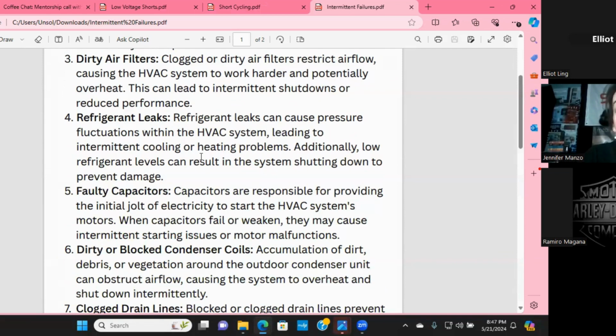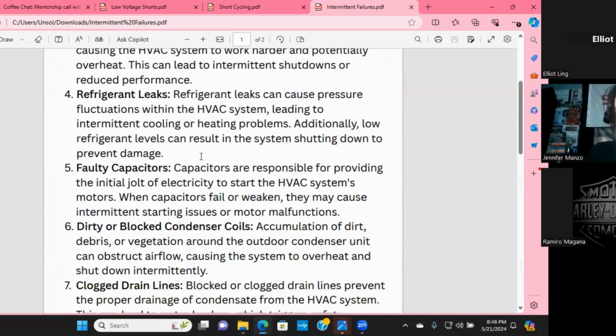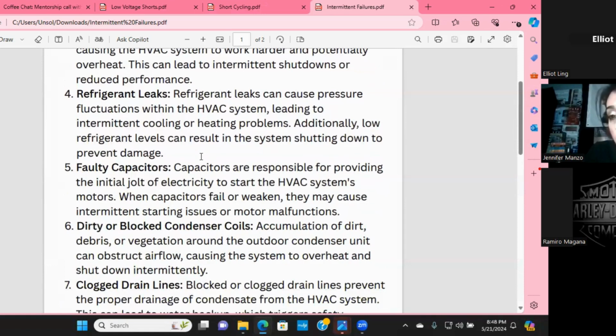Obviously, this is going to cause intermittent problems. Sometimes you'll have enough, especially if we're not talking about dead flat. But if you have just a small undercharge, sometimes there is enough liquid in the condenser and enough vapor in the evaporator where it runs fine. And then 2 minutes later, it just doesn't anymore. The metering device meters it too much or just enough or just a little. And we end up with a system shutting off that will then start back up after thermal overload and run for 2 days. It's crazy.